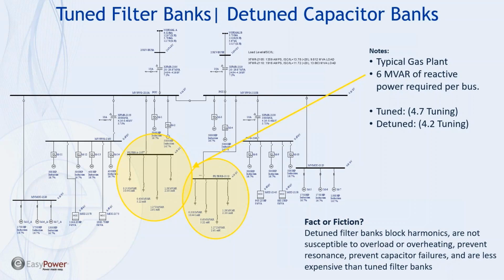It's a project that we just recently did a study on. You can see here in the circles in yellow, you have a 4-stage harmonic filter bank. We would have a choice to either tune that to, say, 4.2, or call it a detuned filter, or tune it to 4.7 harmonic, 4.8, 4.9, something like that, called a tuned filter. Incidentally, I consider both of these systems tuned systems. When you put a capacitor in series with a reactor, and you size that reactor to tune the capacitor reactor combination to a frequency, it's tuned. But there are some engineers out there that like to differentiate the lower tuned filters, those around 4.2, as detuned filters.